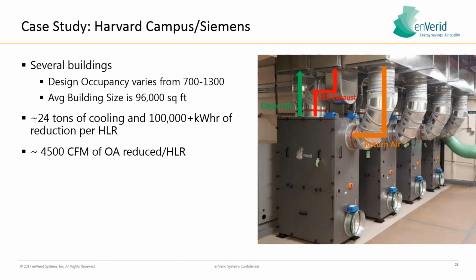So let's take a look at just a really quick real life example here. This is the Harvard campus with Siemens. We did this project with Siemens in Boston. Basically, you have 4 HLR modules here in a mechanical room. They're all in parallel, treating the same return air. We're running that return air through the unit, placing that clean air back into the system, and then we're ducting that exhaust to the toilet exhaust for that once a day time where we go into regeneration for about an hour. And the net result here on this retrofit application was 24 tons of cooling reduction per HLR, and about 4,500 CFM of outside air reduced per HLR as well.